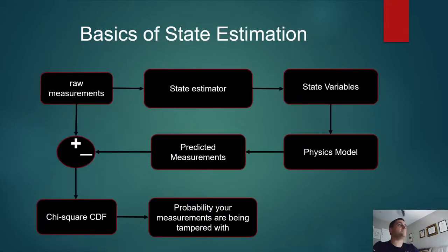The basic idea behind state estimation is you take raw measurements from your sensors. You have a state estimator that you run it through that gives you state variables, which the state variables feed into your physics model, which is similar to the state estimator, to give you measurements that you would have predicted. You then subtract those from the raw measurements that you got and plug the output into a chi-squared distribution function, which will give you a probability that your measurements are either garbage or being tampered with.